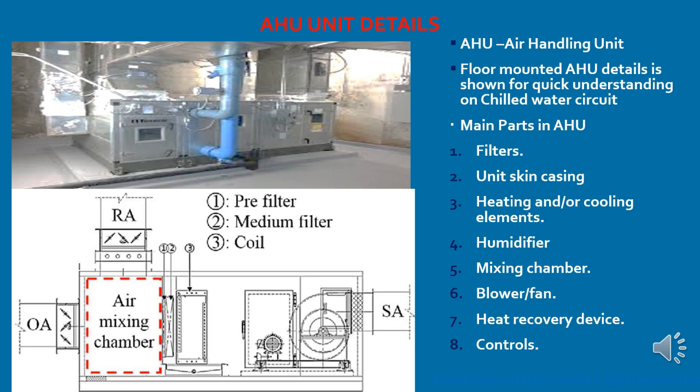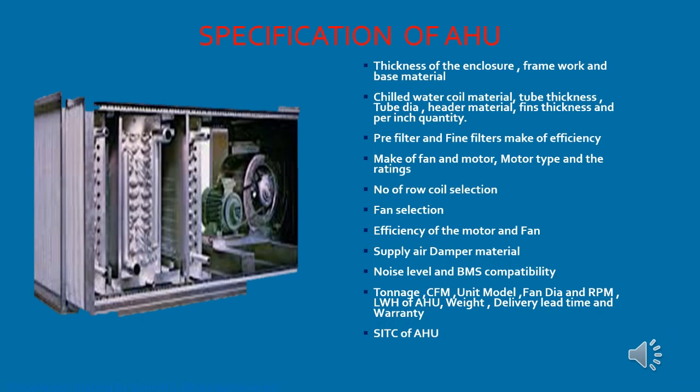Next, a humidifier — whenever we need to add humidity to the air, the humidifier will be used. If humidity needs to be removed from the air, a dehumidifier will be used. The mixing chamber is where fresh air and return air get mixed before passing through the filter. A blower or fan pushes the chilled air into the ducting elements so it reaches the air-conditioned area. A heat recovery device is also used in the AHU, along with controls — electrical control dampers and all related controls.